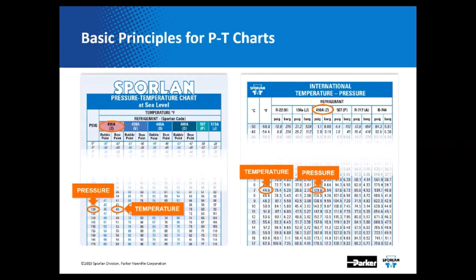This is what our pressure temperature charts look like. What a PT chart is telling you is the boiling point of a refrigerant at a specific pressure. On the left side of this picture, we have a pressure highlighted at 130 pounds, and 45°F would be the boiling temperature. So for 410A, if your evaporator is running at 130 pounds, your refrigerant is boiling at 45 degrees.